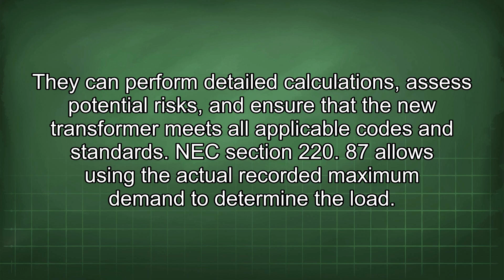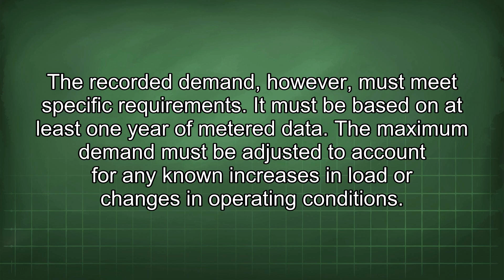NEC Section 220.87 allows using the actual recorded maximum demand to determine the load. The recorded demand, however, must meet specific requirements. It must be based on at least 1 year of metered data. The maximum demand must be adjusted to account for any known increases in load or changes in operating conditions. This method provides a more accurate representation of the actual load than estimations based on connected loads.